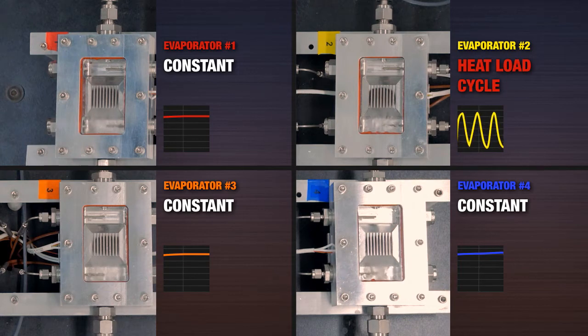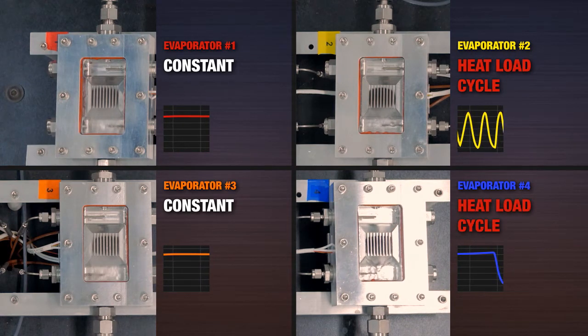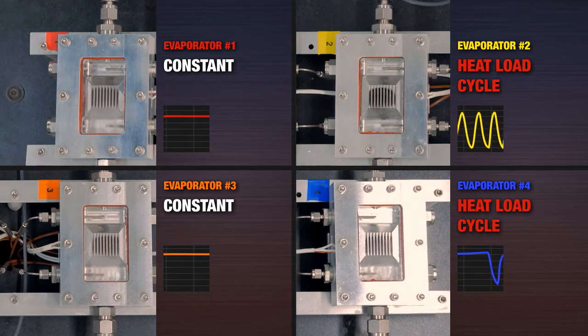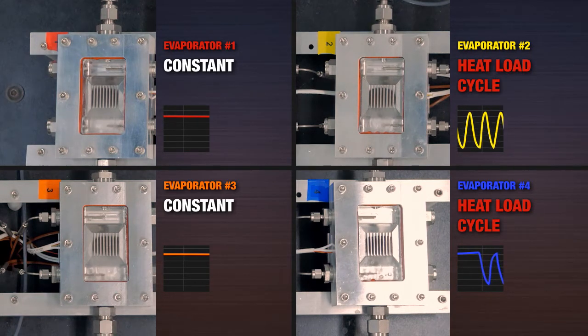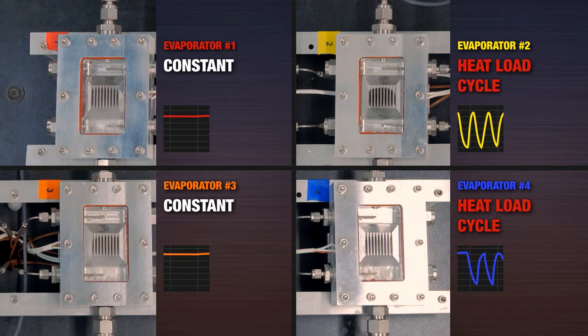We will now begin to cycle the heat load on evaporator four in a similar way as evaporator two. Again, we see erratic boiling at both two and four, but flow rate, temperature, and boiling remain constant for one and three.